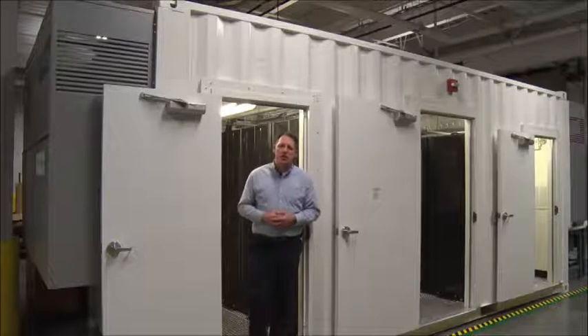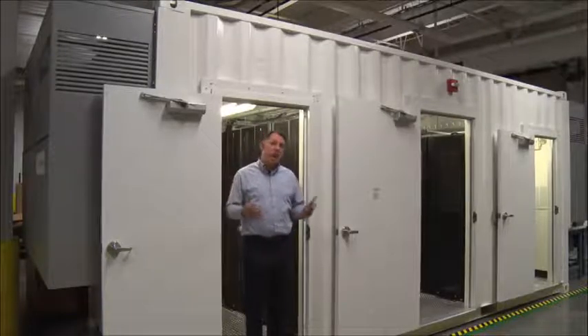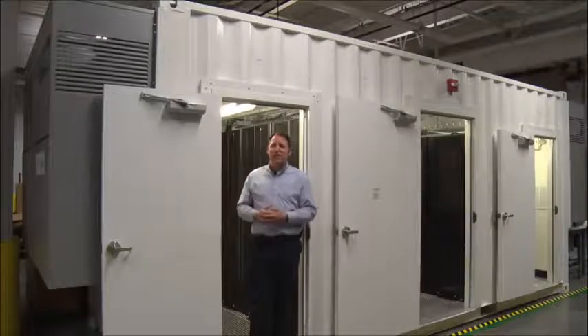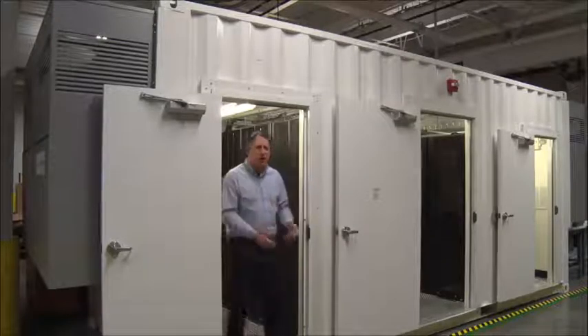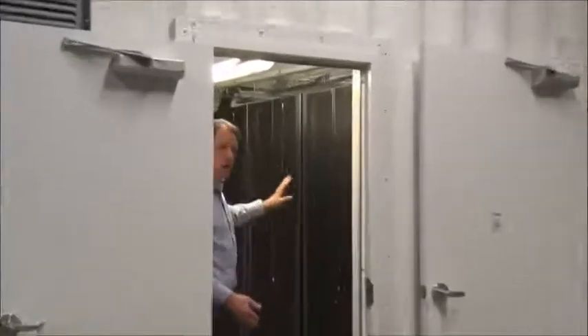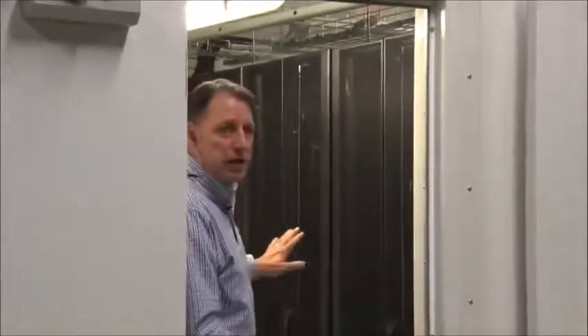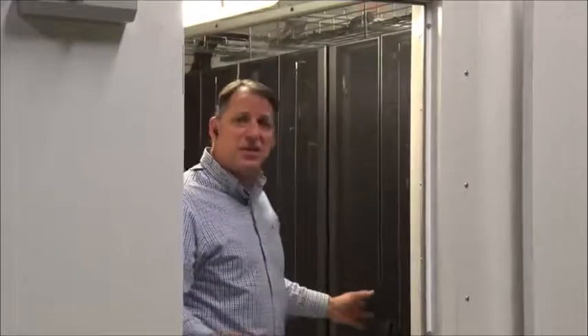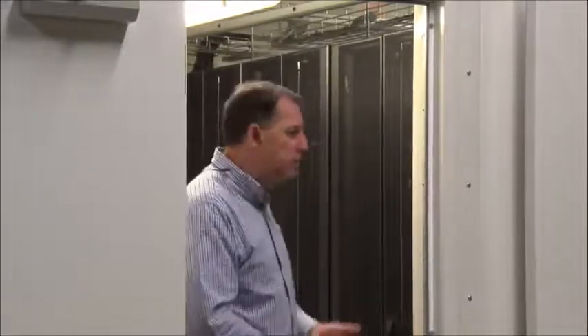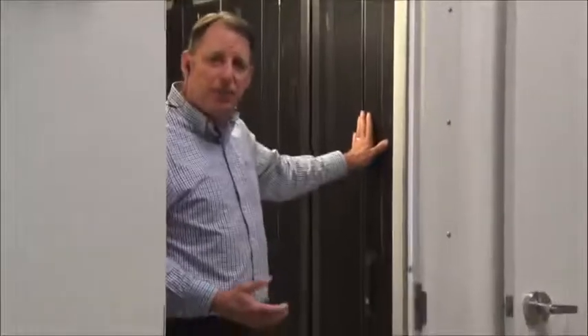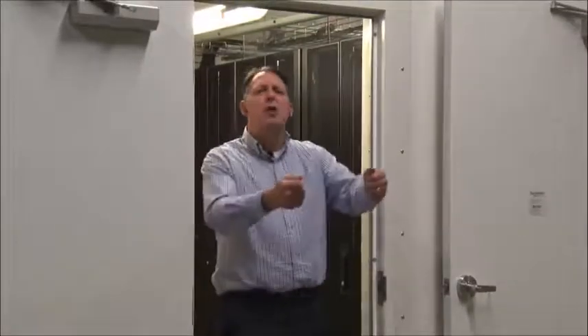There are some challenges with this. Part of it is there's only 8 feet wide to work with and 10 feet high, which gives us some challenges. As you can see inside, I've got 3 racks here perpendicular to the length of the module. 8 feet doesn't give us enough room for full cold aisle, full hot aisle, full rack space, so we have to be creative. We can either mount them perpendicular like this, or set them in line with the length of the module, putting them on slides so we can pull out the racks and work behind them, then push them back in. We have locking rail systems that allow us to do that.